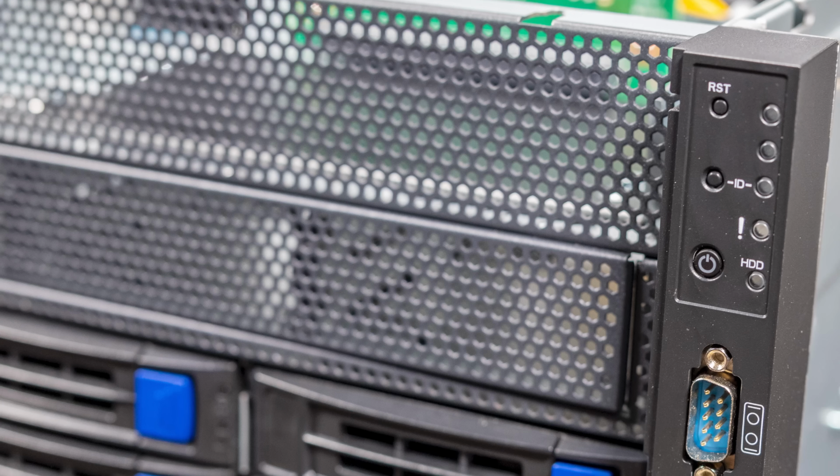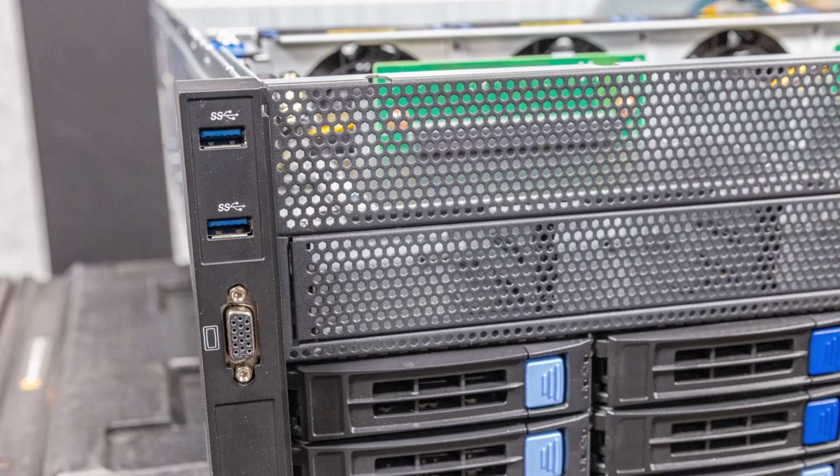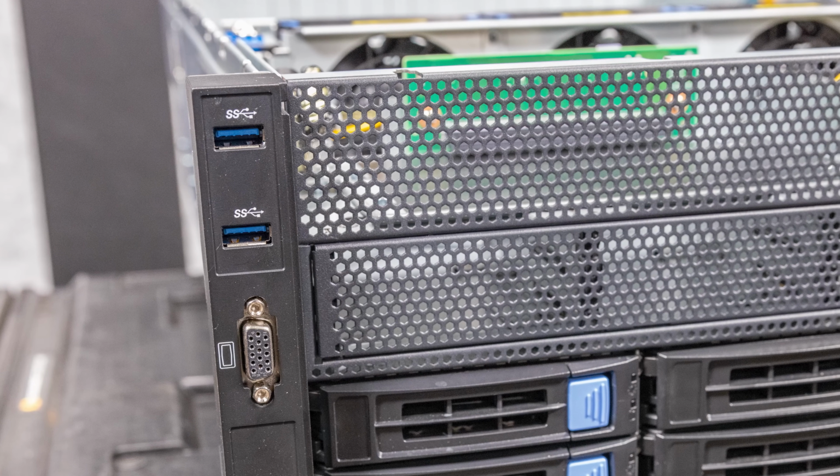And something else that Tyan did that I actually really like on this system is that they do have the front IO. So if you need a serial port, or you need a VGA port, you need USB or any of that kind of stuff, all that's actually on the front of the system. If you've ever been behind a GPU cluster where you have just racks and racks of these systems with all these GPUs in them, you'll know that the hot aisle is actually really hot. And so being able to service with a KVM cart if you need to on a cold aisle is actually a huge benefit because, well, it's easier to deal with a little bit of cold than it is to just get blasted by hot air.